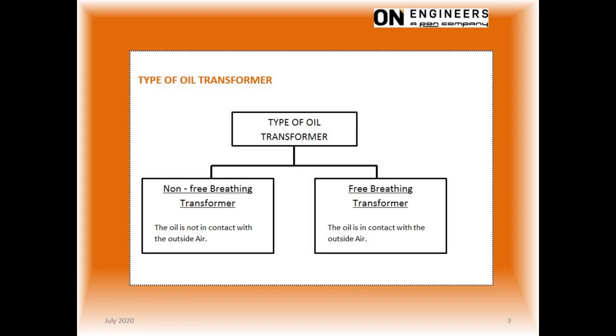This slide describes the oil preservation system of the transformer. The non-breathing type, also known as sealed type, is for smaller size transformers of about 1 MVA. The oil is inside a closed system of the transformer tank and has no contact with the outside air.